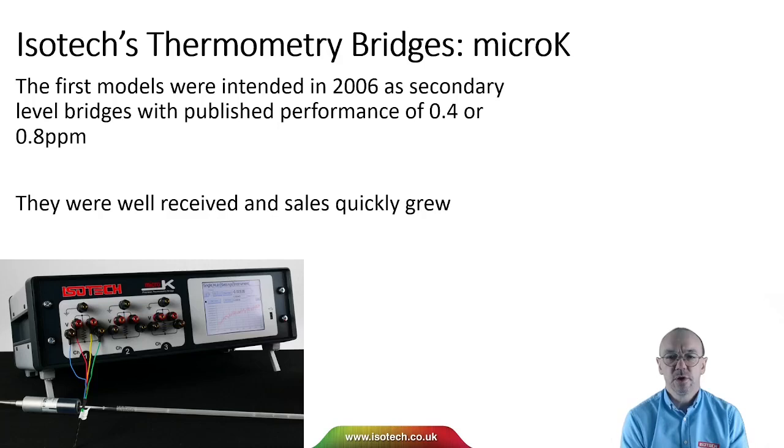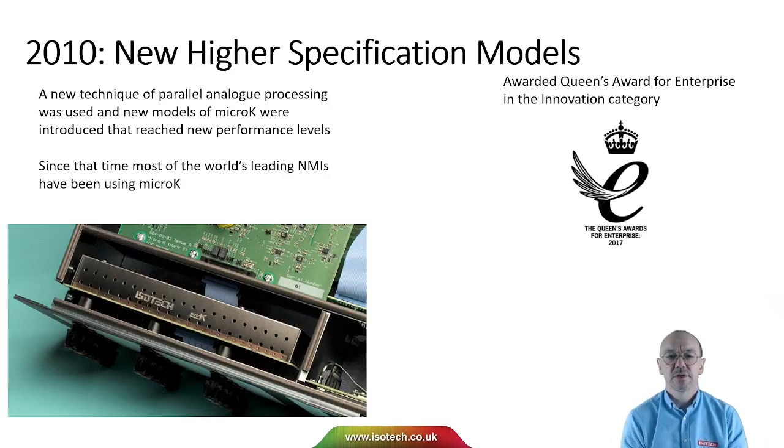Now I want to introduce the Isotech's thermometry bridges — the micro-K range. Our first models were intended for secondary laboratories and were introduced in 2006. At that time the performance was 0.4 or 0.8 ppm. They were very well received and sales quickly grew. In 2010 we introduced higher specification models using a new technique of parallel analogue processing, which reduced noise to new performance levels. Since then many national metrology institutes around the world have been using the micro-K, and we received the Queen's Award for Enterprise in the innovation category for its development.